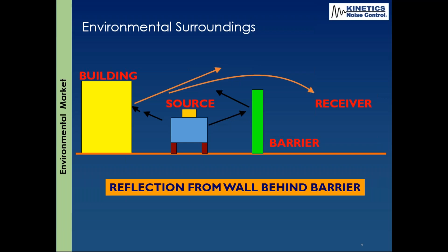In our application, we have a wonderful situation where the receiver is 5 feet from where you can see I have all my arrows, and you see in that concrete equipment yard, you're going to find there's a lot of reflective surfaces. It's cinder block, and it's actually magnifying the sound energy and the noise that the chiller's making. If the chiller was sitting in the middle of a parking lot somewhere and you were 50 feet away and there were none of these reflective surfaces, it would be of a certain sound level once it reaches you in sound pressure.